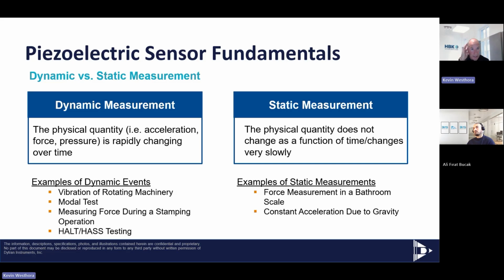The other thing would be your data acquisition system. If your system is set up for IEPE sensors, you don't want to pick a MEMS sensor because you'd have to power it externally. But conversely, if your system is set up for DC power, you would probably be better off picking a DC MEMS accelerometer and using a simple 10-volt DC power versus trying to power IEPE externally or getting another card for your data acquisition system. So that's usually what dictates the type of sensor. I would say, though, in my humble opinion, you would never use a DC MEMS accelerometer unless you need 0 hertz frequency. And many customers do, if you're in the aerospace industry or automotive, many applications require 0 hertz frequency. Then you must use a DC MEMS accelerometer. But if you don't need that, then I would always use a piezoelectric sensor because they're cheaper and they're smaller in size.